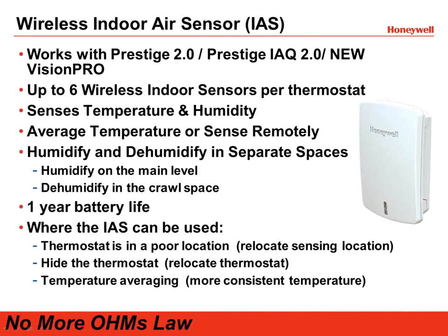Indoor air sensors. This is by far one of the exciting, might be a little too much, but we're able to wirelessly connect up to 6 indoor sensors per thermostat, and this has been great for averaging or moving a thermostat or taking temperature readings from a spot that was hard to get to with wires. So it's been a great lifesaver for me, just dealing with some of the jobs when we can remotely put this thing anywhere we want. So it's been a great little option for the Redlink thermostats.